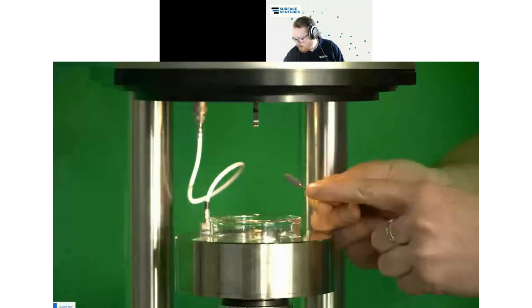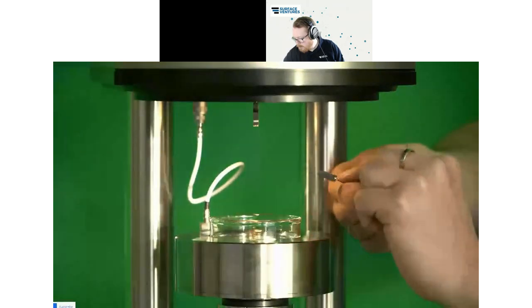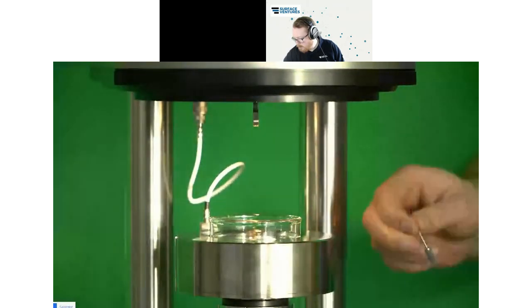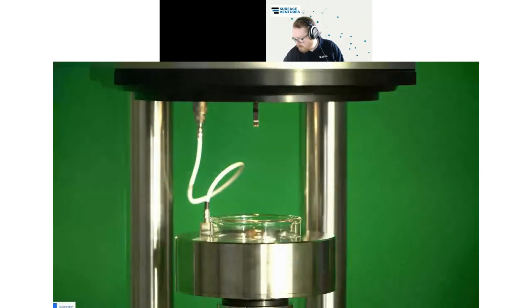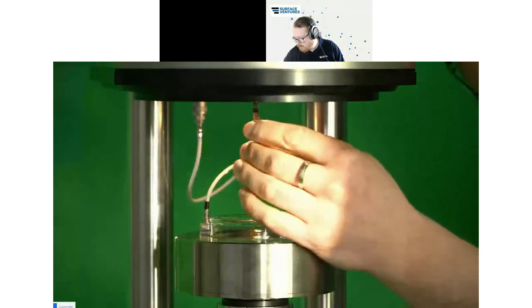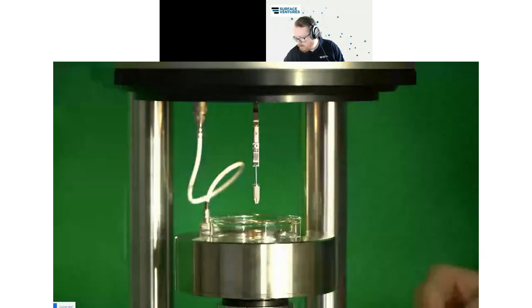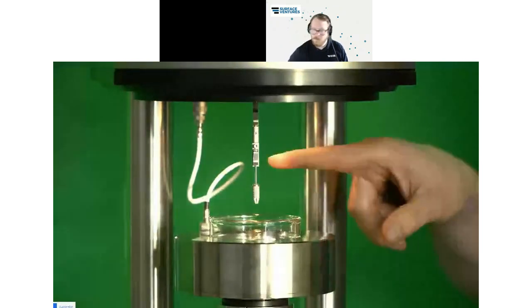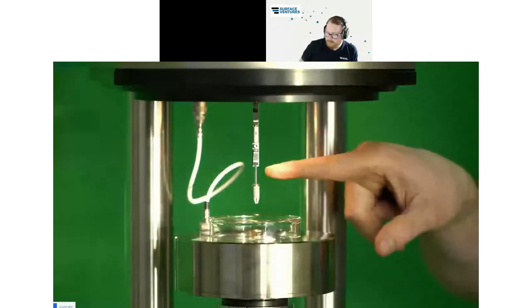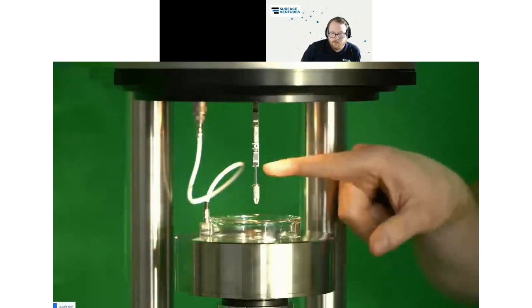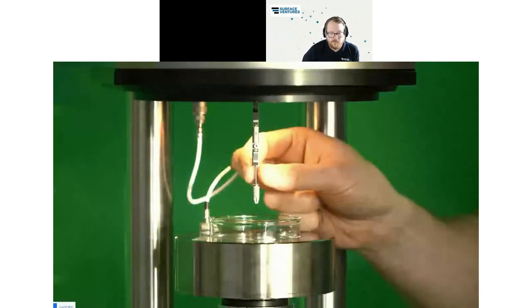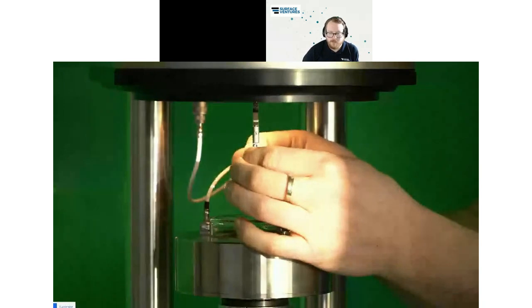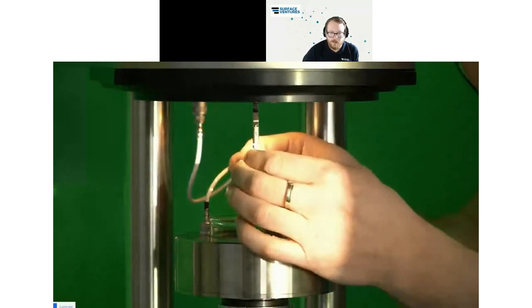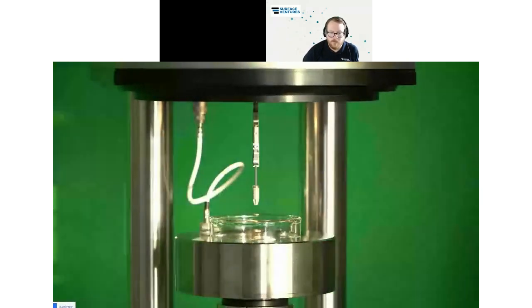And we use these screw holes now to fix a little rod inside. And then with this rod, we can attach it to our tensiometer. What I want to show you first is I use here now a little extension so that it becomes a bit longer and goes deeper down. But now we have our final setup. So now we have the tooth implant here. It is mounted inside our device. And now we can start the measurement. I just need to lower my implant a bit. I pushed it up too much, but like this now it's okay.